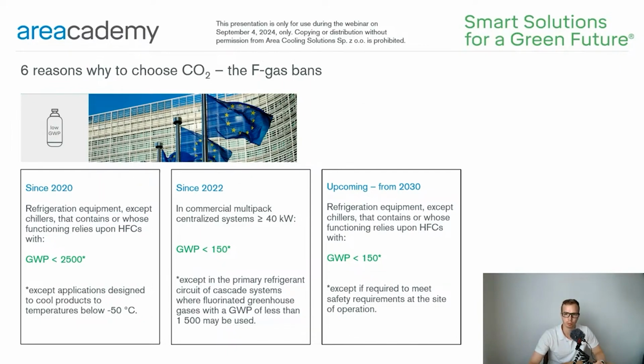In the updated European F-gas regulation, you can also find the corresponding bans for our sector. And here I decided to present 3 restrictions for the stationary refrigeration units. The first, which has been in force since 2020, bans the HFC refrigerants with a GWP factor of 2500 or higher. This means that the popular 404 refrigerant can no longer be used. However, we can still use the 448 and 449 refrigerants.